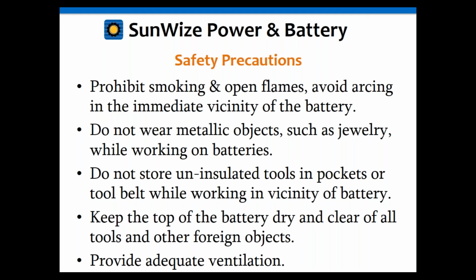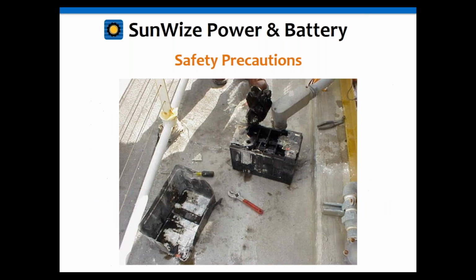Already mentioned uninsulated tools again. Not just using them, but also something in your pocket that may fall out onto the batteries, or anything in your pockets that may fall onto the batteries. You may want to avoid that, as well as keeping the top of the batteries clear and dry away from things that might fall on it. That's also going to be important with enclosures. One function of an enclosure is to keep things from falling on the batteries. And you want to avoid stuff like this, this is not good. This is what happens when batteries get shorted out.